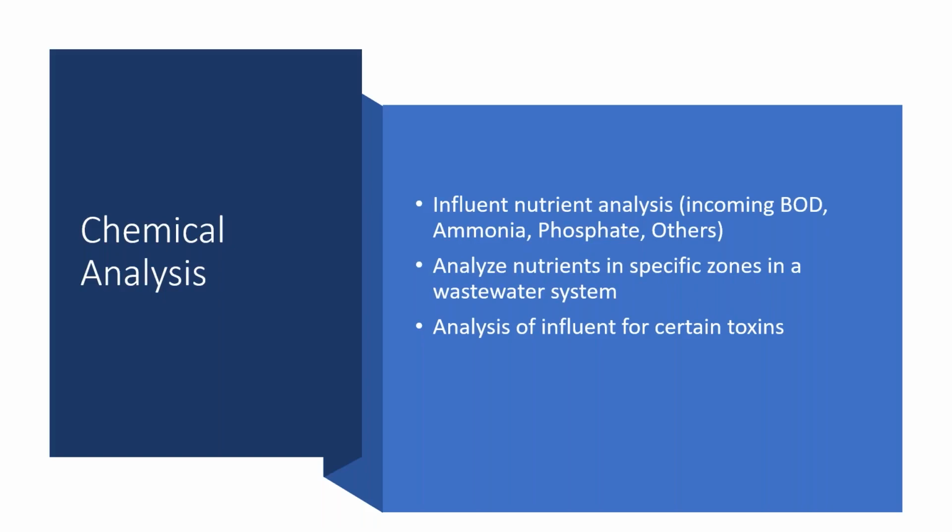So for example, you could have an aeration basin which has a sludge deposit at the base of it, and you could have pockets of anaerobic activity in your typically well aerated basin. But this pocket of anaerobic sludge might be pumping excess ammonia back into your aeration basin, which might be contributing to increased ammonia leaving in your plant effluent. And you might be confused if you were to just analyze the influent, because you might not have any changes in what your influent composition has been.